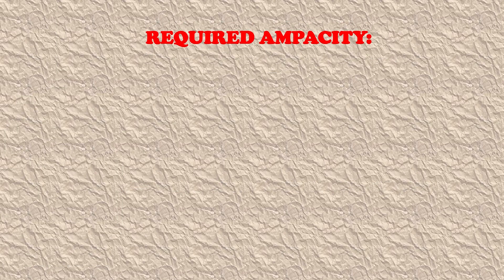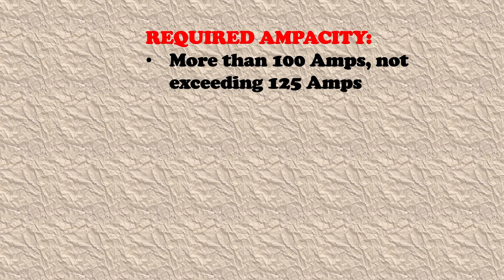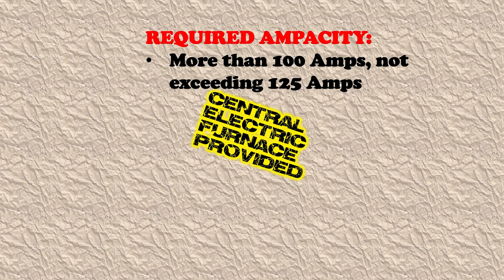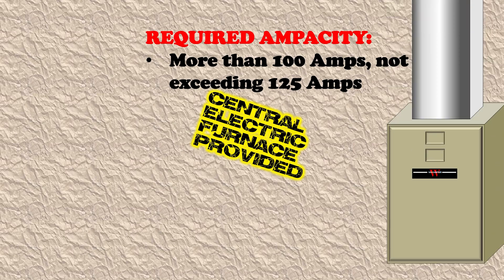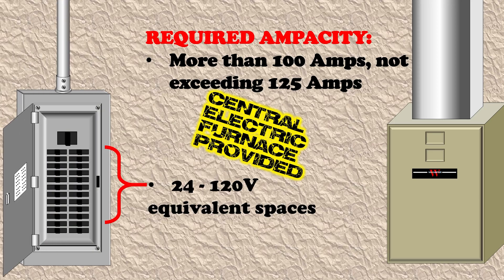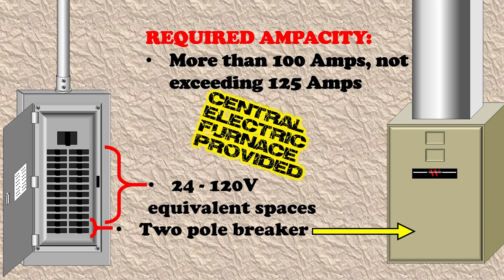In this next example, our required ampacity is more than 100 amps but not exceeding 125 amps inclusive, and a central electric furnace is provided. If a central electric furnace is provided, we once again only require 24 of those 120-volt single pole equivalent spaces. The idea being that this central electric furnace only requires a two-pole breaker to supply it, therefore not needing the extra spaces that would be required if we don't have the central electric furnace provided for.